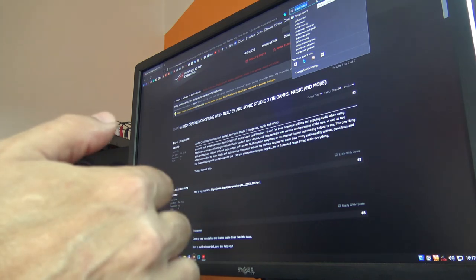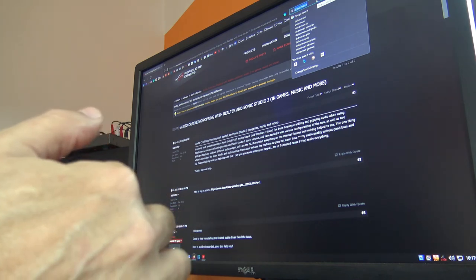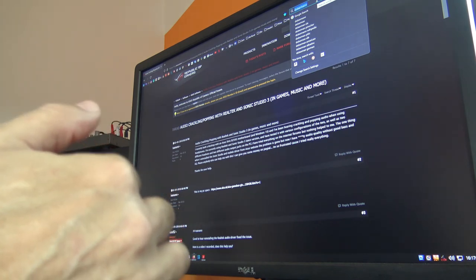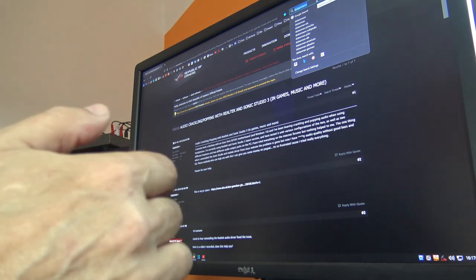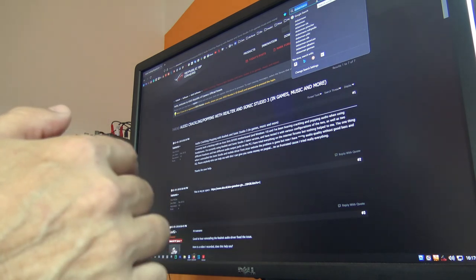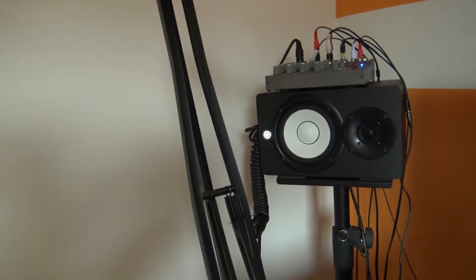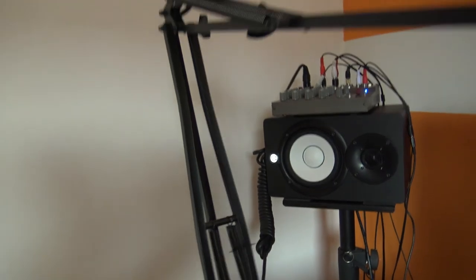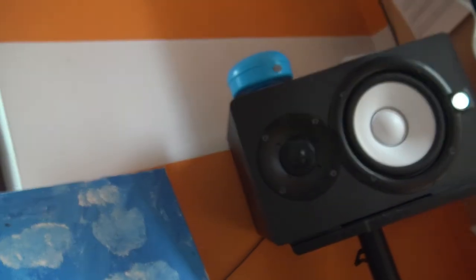The idea is that now the ground of everything in the audio chain is related to a single socket and a single point. Having multiple ground points - each of these Yamaha monitors had their own power supply and their own connection and grounding. That was the idea - to have just a single point of grounding.